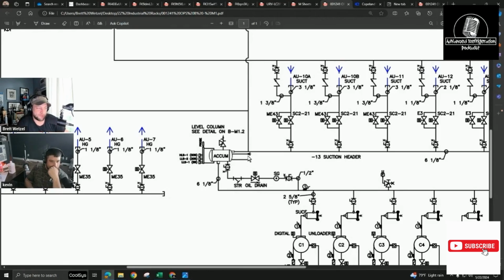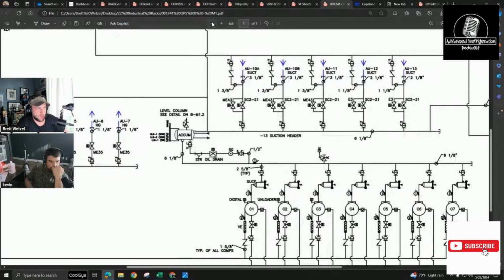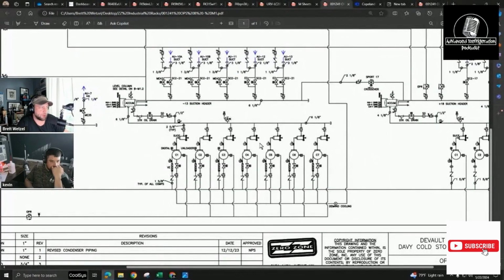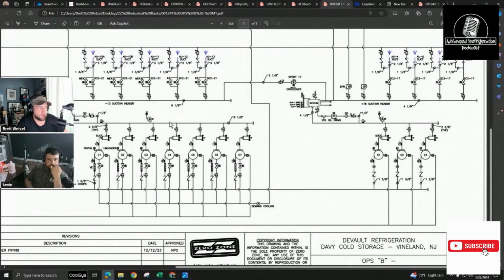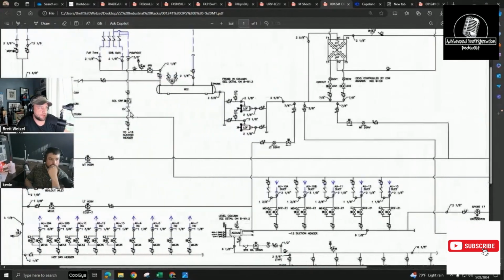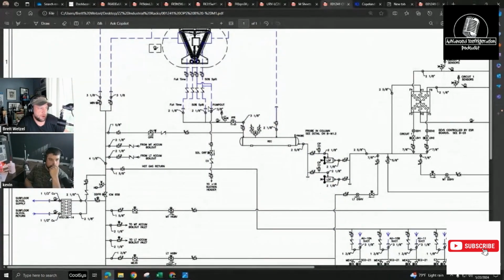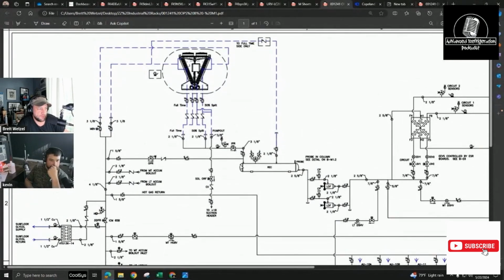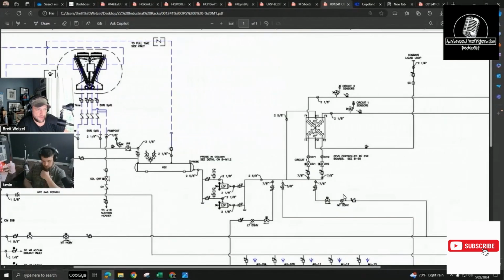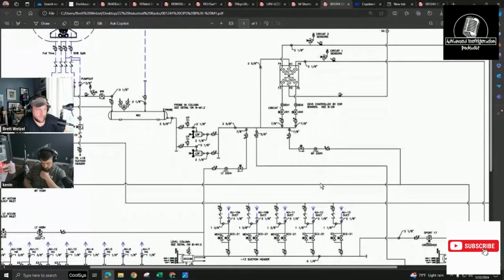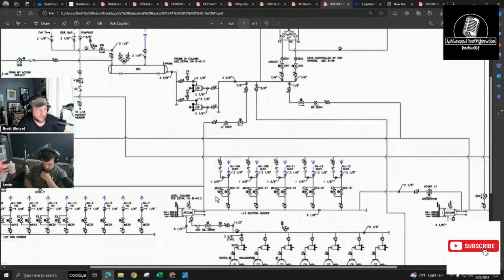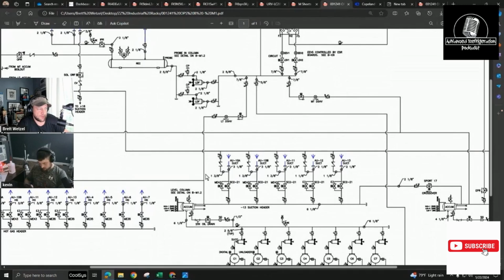On top of that, you've got these 2 lines right here. Typically they'll do one of 2 things, and I'd have to follow the piping to see that. Either they'll run the drain leg of the condenser... let's see if they do it here. So here's your condenser, through your receiver, through a heat exchanger to common liquid. Medium temp discharge valve. No.